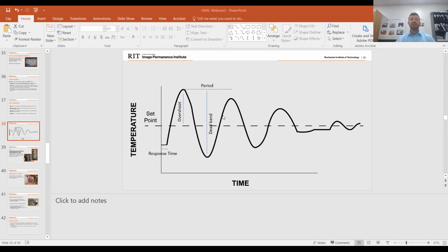There could be significant energy savings. We've worked with institutions in hot, humid climates, in libraries that were built in the 20s, that could shut their system off for 4 to 6 hours in the summer, in the evening. Even in the summer, in a bad building, they got significant energy savings from shutting it down. So I definitely would recommend investigating shutting that system down. There has been concern in the past that turning it off will cause a lot of wear and tear on motors. I've been told that that's been debunked, that the theory isn't entirely true, that you don't put as much wear and tear on motors as was believed. So the concern over burning the motors out isn't as strong as it once was.